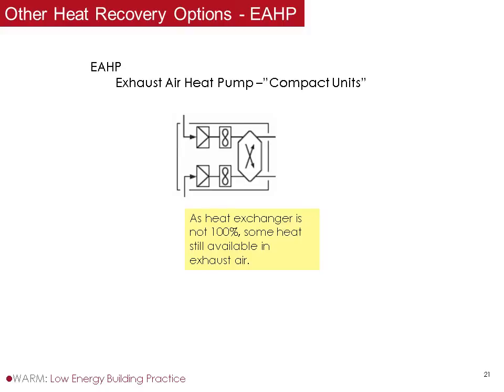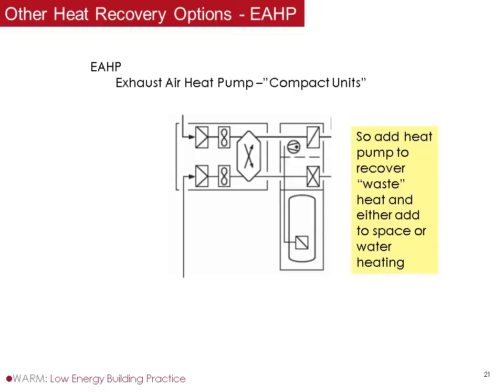The other thing to look at briefly is the EAHP, exhaust air heat pump. In passive house terminology we call them compact units. The idea is that the heat exchanger isn't 100% efficient, more like 85 or 90%, so some heat is still available in the exhaust air. What they do is put a heat pump on the back to recover that, and you can put it either into space heating or, usually, into water heating.